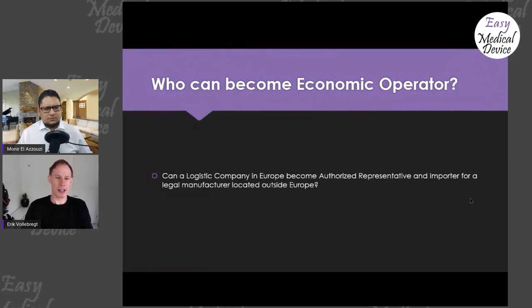because an importer is any entity that fits the definition of being an importer. So in order to see if you're an importer, you would need to be the first entity established in the Union to place medical devices on the market. You could say that's something you can assign somebody to do because of the way the agreement with the importer works, but legally you can't appoint somebody to be your importer. So it's an important difference between the two.